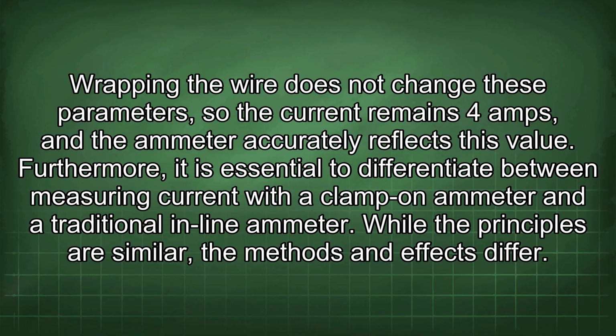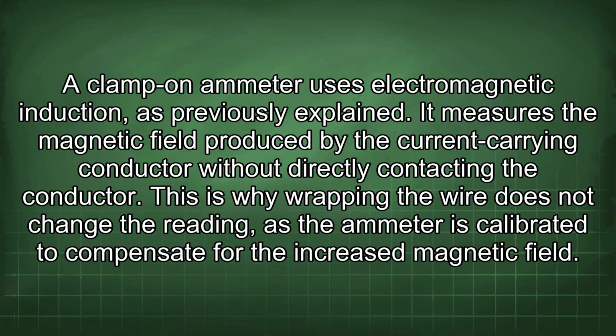Furthermore, it is essential to differentiate between measuring current with a clamp-on ammeter and a traditional inline ammeter. While the principles are similar, the methods and effects differ. A clamp-on ammeter uses electromagnetic induction, as previously explained. It measures the magnetic field produced by the current-carrying conductor without directly contacting the conductor. This is why wrapping the wire does not change the reading, as the ammeter is calibrated to compensate for the increased magnetic field.